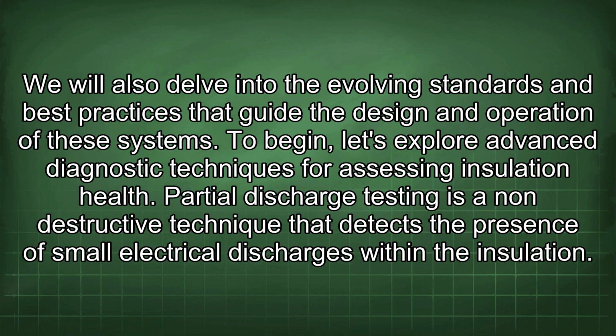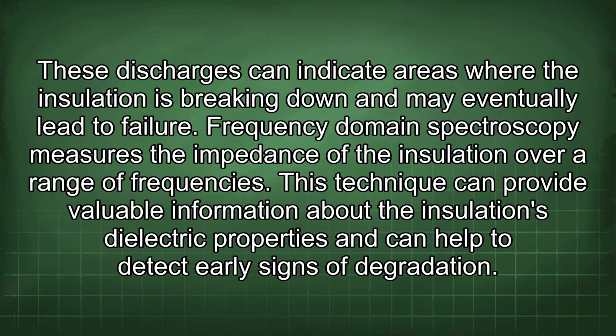Partial discharge testing is a non-destructive technique that detects the presence of small electrical discharges within the insulation. These discharges can indicate areas where the insulation is breaking down and may eventually lead to failure. Frequency domain spectroscopy measures the impedance of the insulation over a range of frequencies. This technique can provide valuable information about the insulation's dielectric properties and can help to detect early signs of degradation.